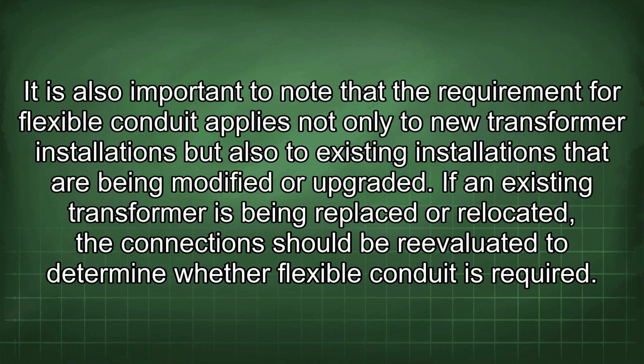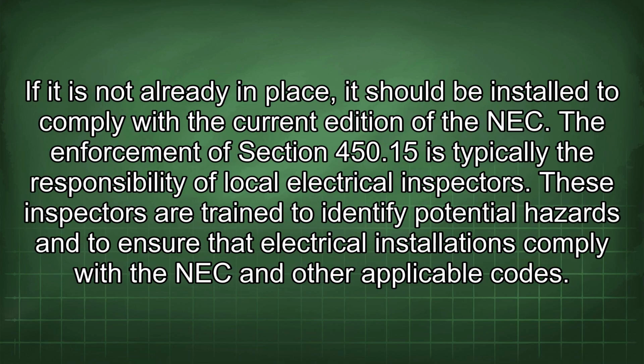It is also important to note that the requirement for flexible conduit applies not only to new transformer installations but also to existing installations that are being modified or upgraded. If an existing transformer is being replaced or relocated, the connection should be re-evaluated to determine whether flexible conduit is required. If it is not already in place, it should be installed to comply with the current edition of the NEC. The enforcement of Section 450.15 is typically the responsibility of local electrical inspectors.